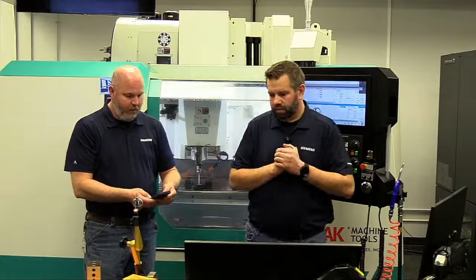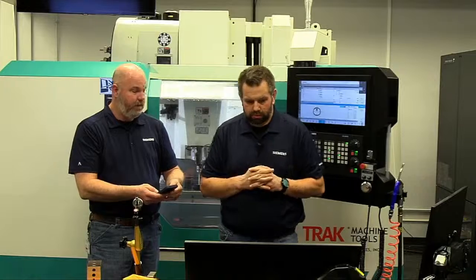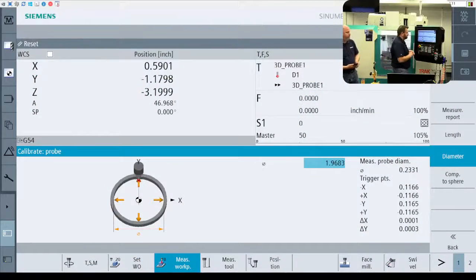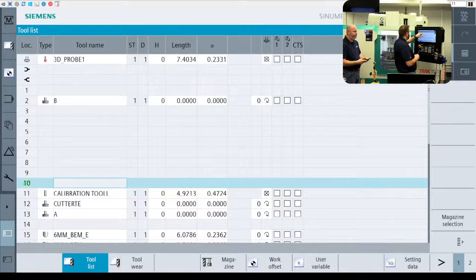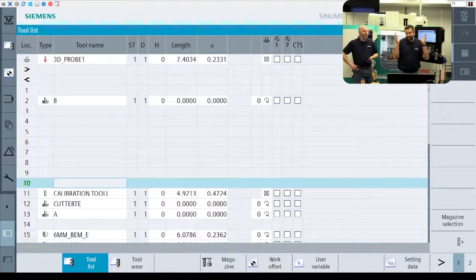Why after calibration is the probe ball not 6 millimeters in the tool offset table? So if we look at our offset screen here, we don't have a perfect 6 millimeters on that stylus, and it's because it's actually taking into consideration the trigger in the probe, that lag. There's a little bit of lag in the probe, and that's taking that trigger into account. And we want the control to do that because it's going to predict that lag on every hit. So we know the trigger inside the probe is happening, and we want to know what that is. So that's why we're not getting a perfect 6 millimeter number.